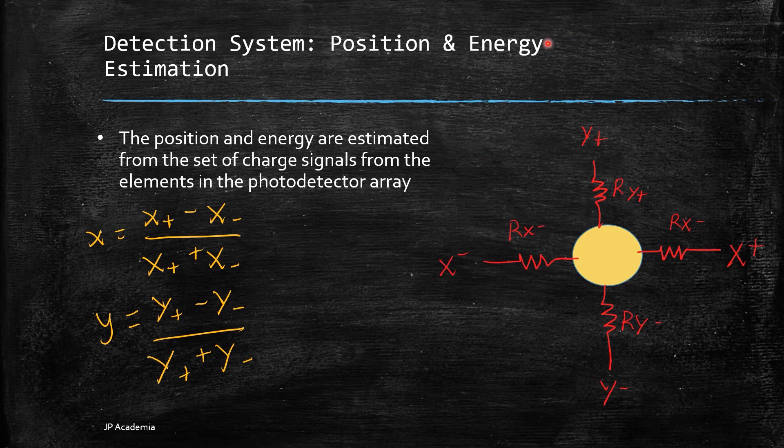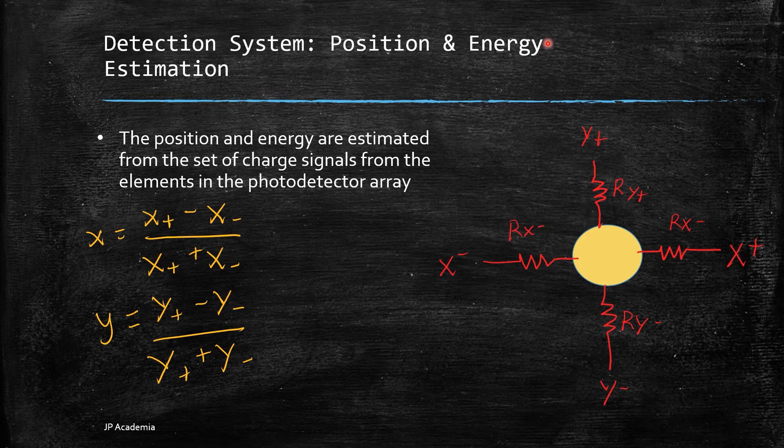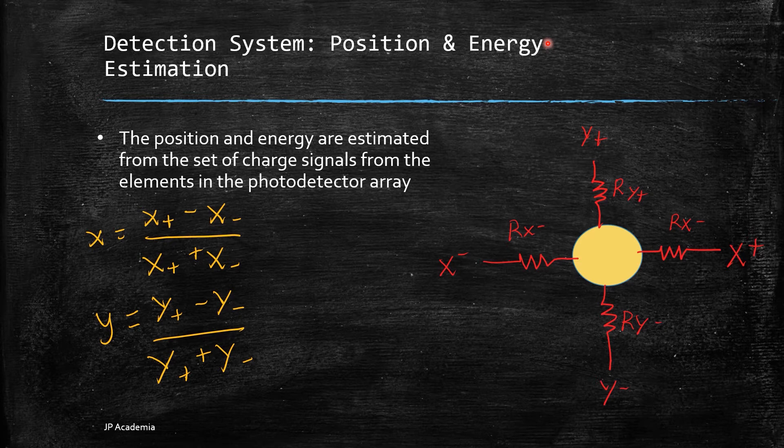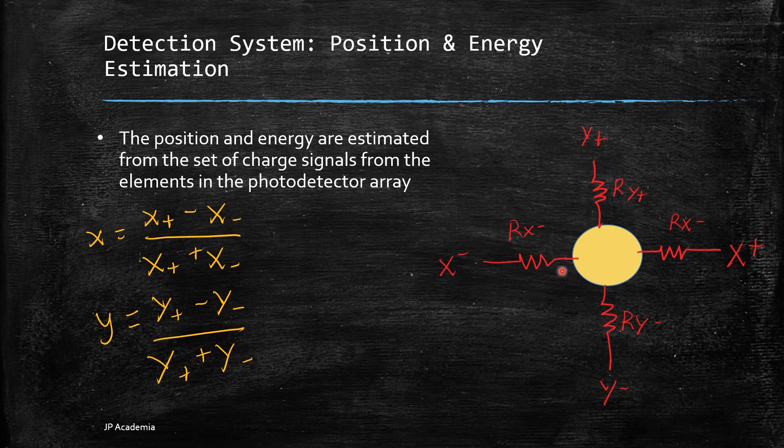In early gamma cameras, the computations above were performed using analog circuits. In current systems, the computations are performed digitally. However, this equation does not perfectly map the source position given that our PMT signal does not actually vary linearly.